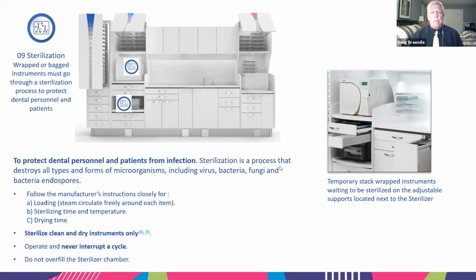Now, I've had some people with a sterilizer who take all the racks out, keep just the bottom shelf, and stack 5, 6, 7 cassettes up. That's a no-go, you can't really do that. But if you keep the cassettes in the rack, it's impossible to overload a sterilizer.